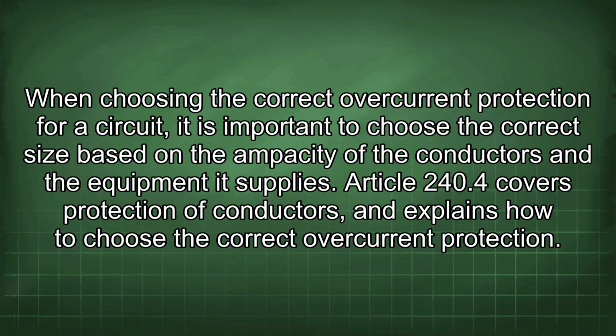When choosing the correct overcurrent protection for a circuit, it is important to choose the correct size based on the ampacity of the conductors and the equipment it supplies. Article 240.4 covers protection of conductors and explains how to choose the correct overcurrent protection.